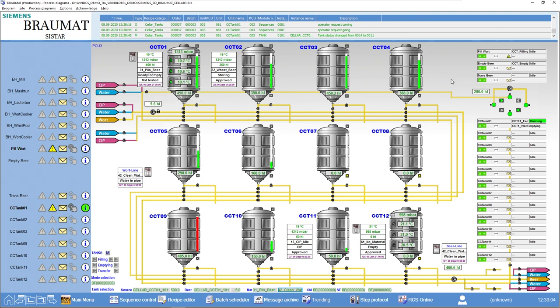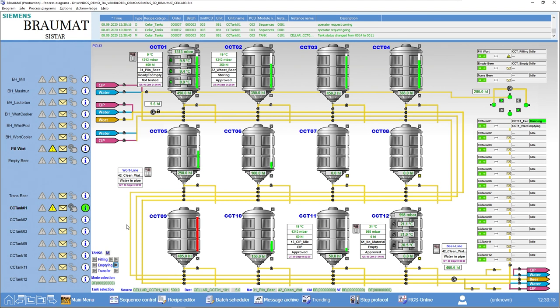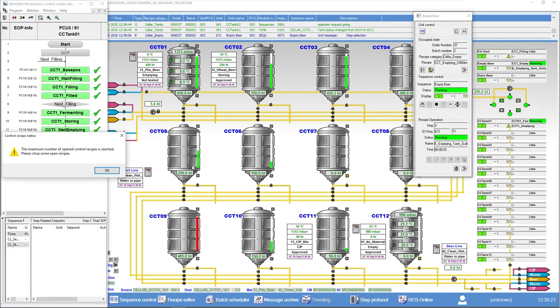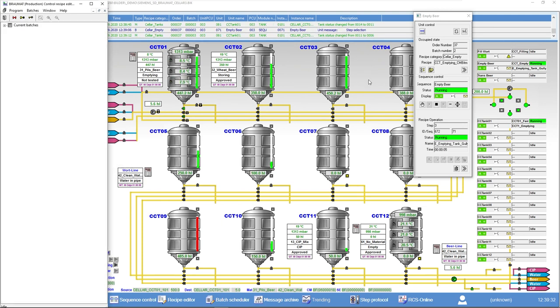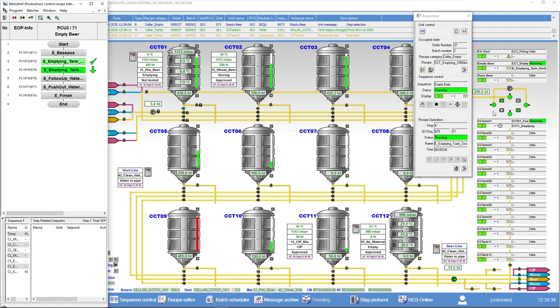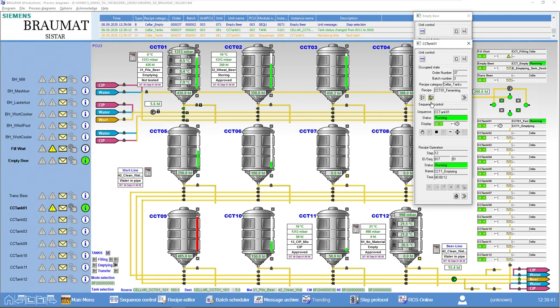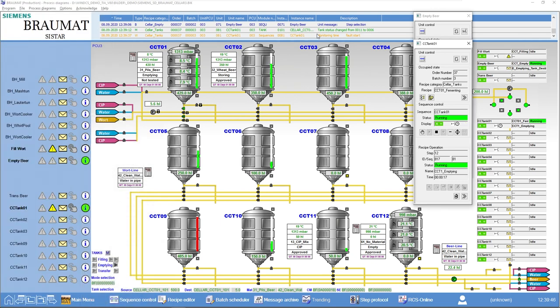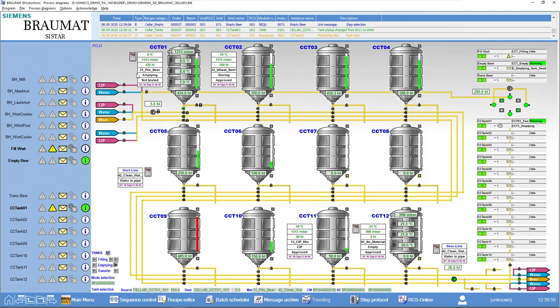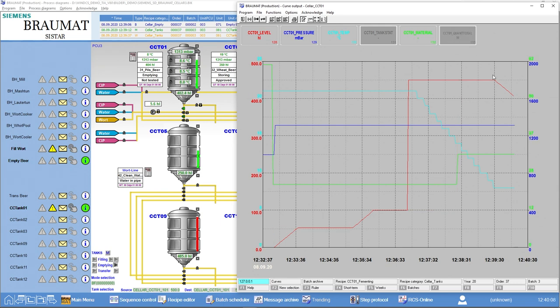Empty means I can now combine it with a new subsystem again. I can control this again through the order system. But I can also make a selection in the process image and start an order accordingly. Or a batch, which is running now. This is synchronized again via handshake signals with the actual tank recipe that is underway. This means that the tank recipe is currently undergoing the empty step. We channel the corresponding new product through the beer line to filtration and empty the tank. Again, this can be seen in the trend image.